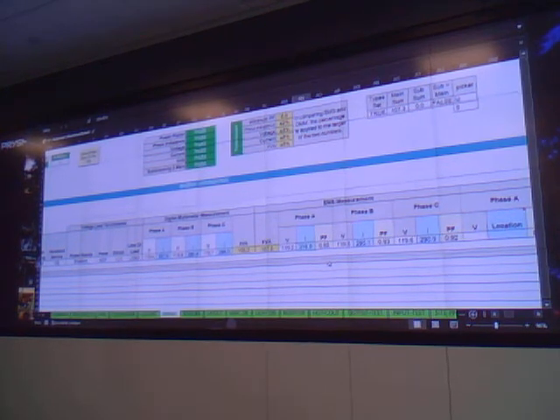Well, that's because it has electric heat. But it says there's no phase imbalance though, so would it still be the phase thing? So the power factors are all calculated from the voltage and the amperage. Is this hypothetical, or is this an actual reading? Those are actual readings, and that's still really high.